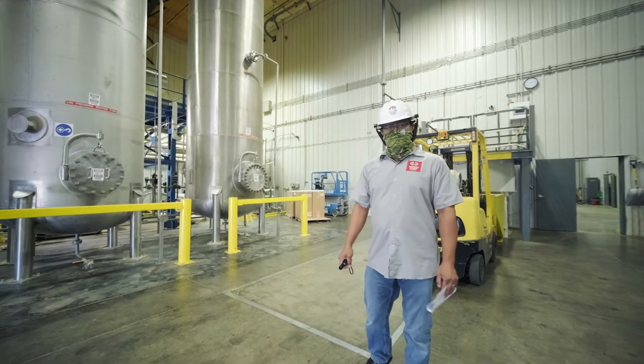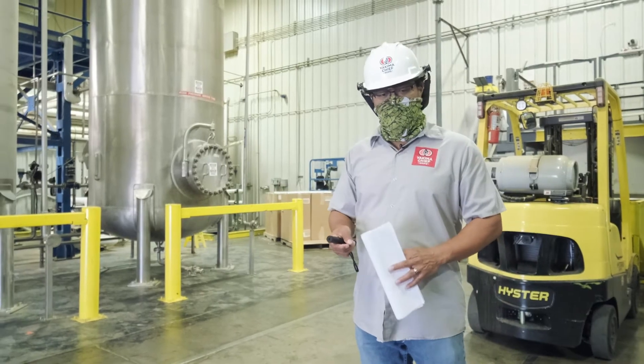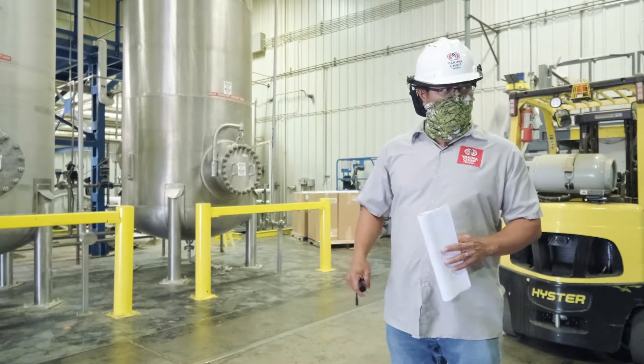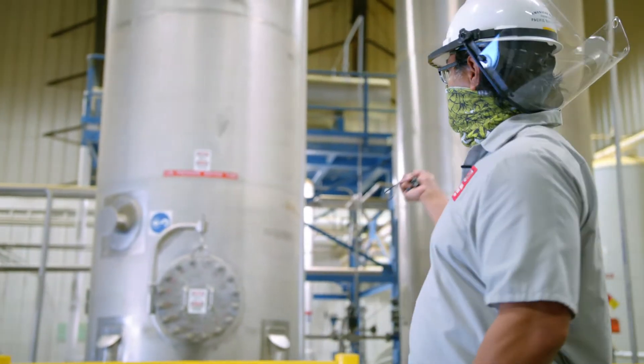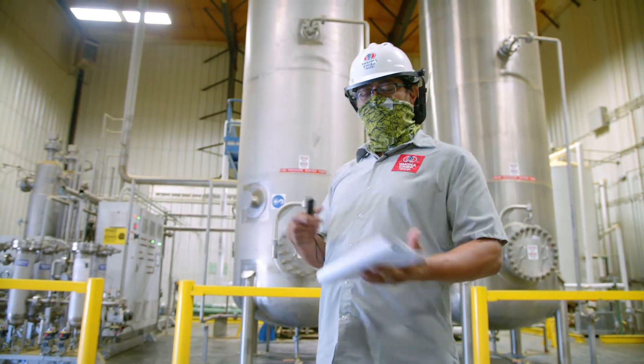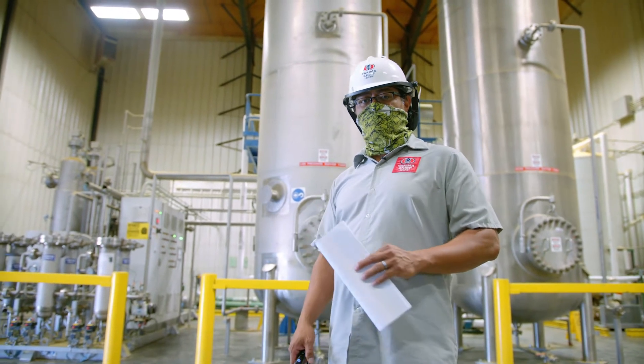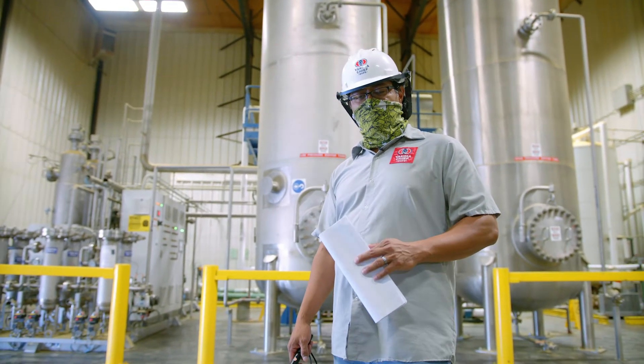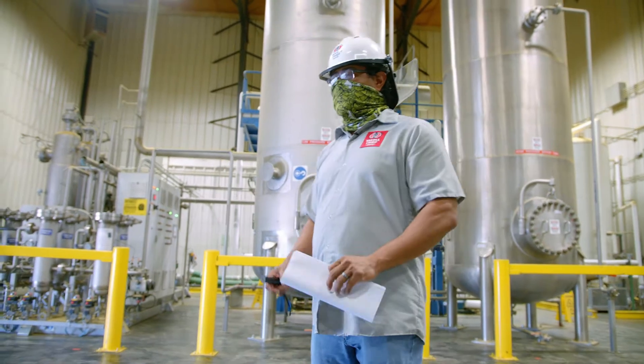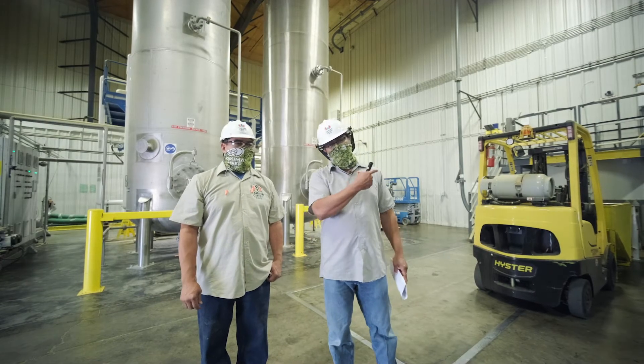Now I'm going to talk to you about our fairly new CO2 recovery plant. We're essentially taking the vented CO2 gas that would otherwise go into the atmosphere. Instead, we're collecting it into these two buffer tanks — a high pressure and a low pressure buffer tank. At the end of that cycle, we are producing beverage grade CO2 at an average of about 565 kilos per extractor. The efficiency of the system is 90%. Pablo, we'll see you later — let's go check out the extract plant.